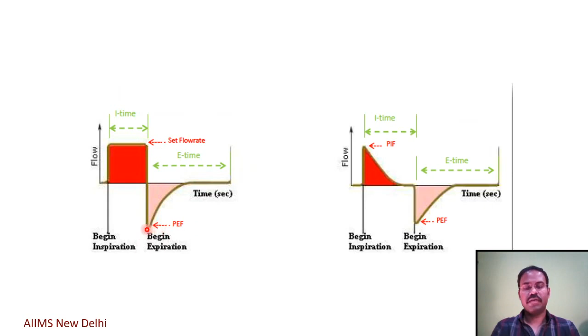Now the basic difference between these two types of flow time scalar, the constant flow versus the descending or decelerating flow, is that in constant flow, the flow is maintained constantly during the entire phase of inspiration, so the pressure gradually keeps rising till the end of inspiration when it reaches the peak inspiratory pressure. Whereas in a decelerating flow pattern, the peak flow and the peak pressure are achieved at the beginning of inspiration, and the pressure is maintained constantly throughout the inspiratory cycle as the flow decreases.